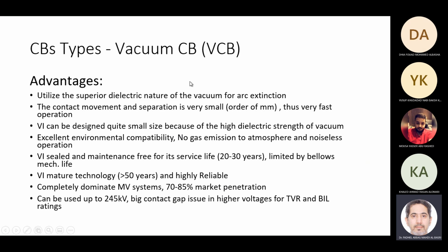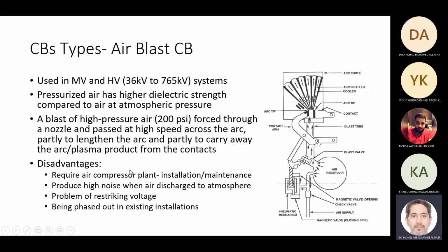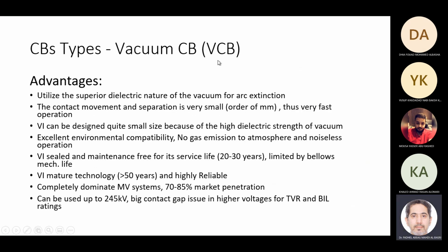We have vacuum. So what does air blast require? Pressurized air. It is very noisy. This is also being phased out nowadays. Nowadays mostly vacuum is used for medium voltage applications, and SF6 for high voltage applications. So in vacuum, vacuum normally has very superior dielectric properties.